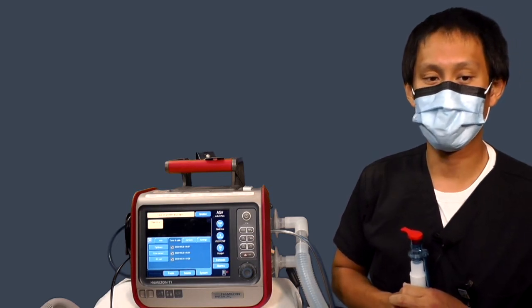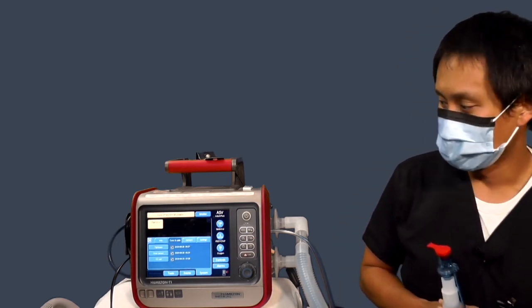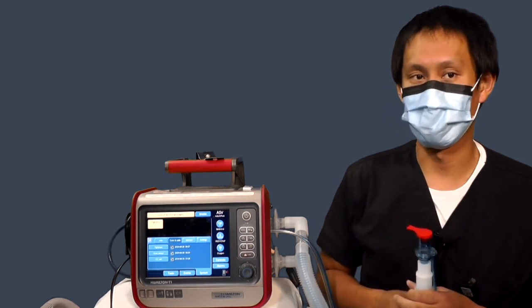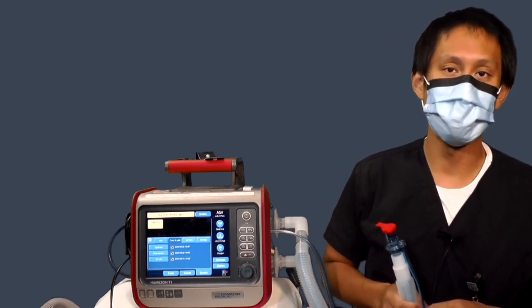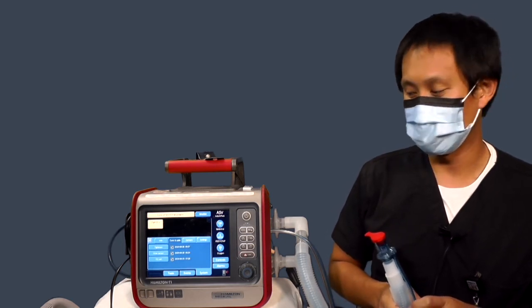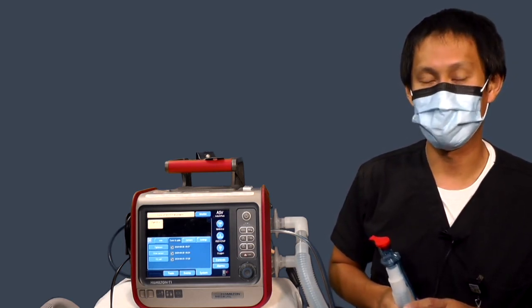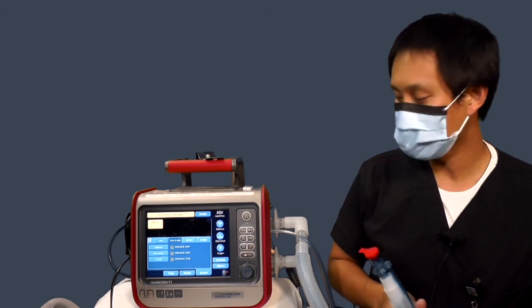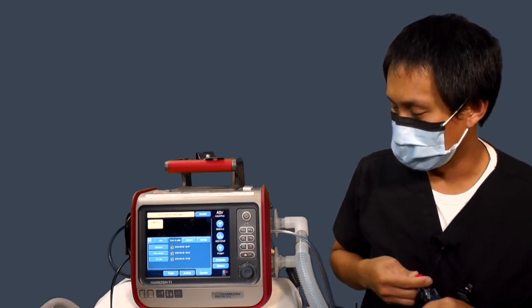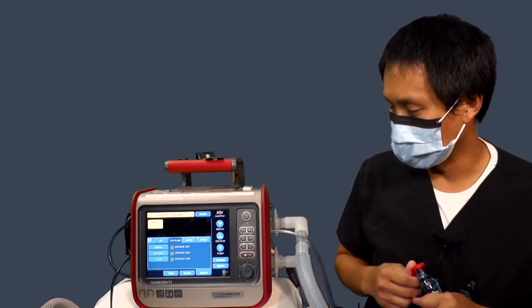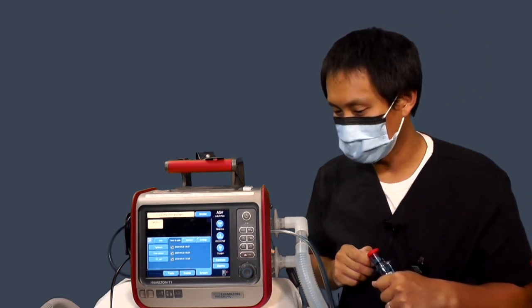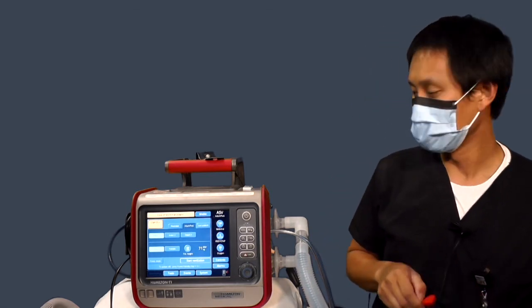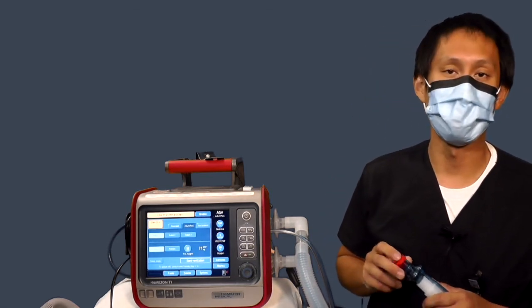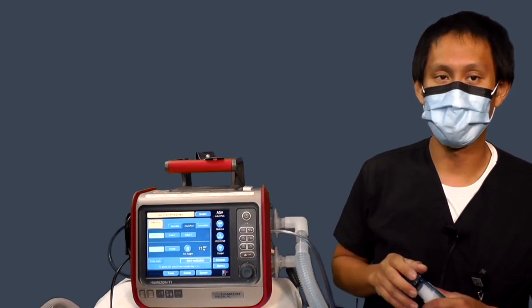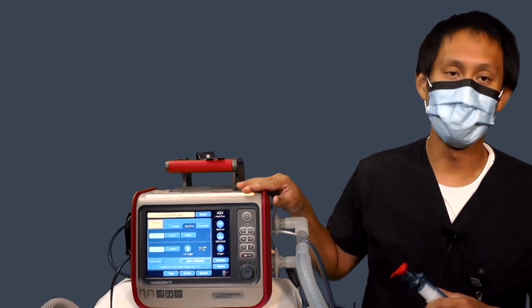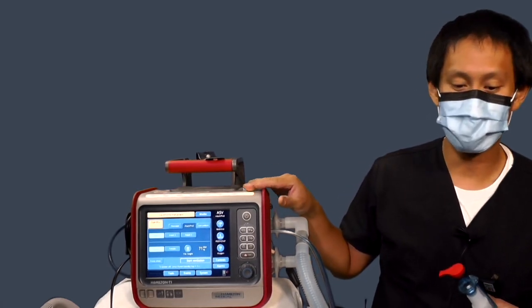You'll notice there's 3 options on the screen. There's a tightness option, a flow sensor option, and an O2 cell option. You do not need to do the O2 cell option, but you do need to do the first 2, the tightness and the flow sensor, before you use it on a patient. If you're concerned for time, or you have your workflow so that you do this when you're coming on your shift, you can do your calibration ahead of time and then leave it on standby. It'll save your calibration on the ventilator until you're ready for use.